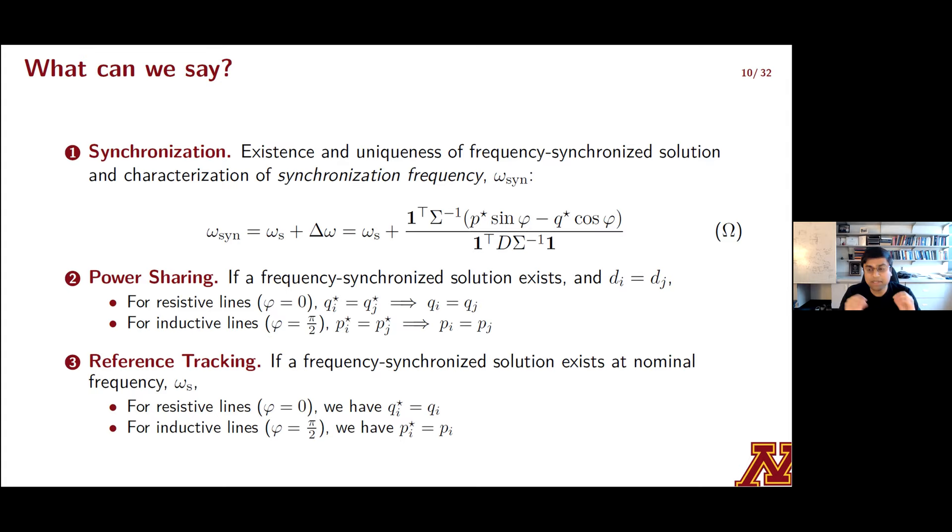If you stare at delta omega, you'll see that it depends on a weighted sum of power set points. These are the terms p star and q star, as well as the transmission line impedance angle, this quantity phi. And then you'll see that if the references sum up in a very particular way to zero, and we term this condition as balanced, there is no frequency offset, and everything is synchronized to the electrical radian synchronous frequency. Let's move on to power sharing. If you have a synchronized solution, and if you make that further effort of tuning the steady state droop characteristics of the different GFM IBRs to coincide, what you get is power sharing.